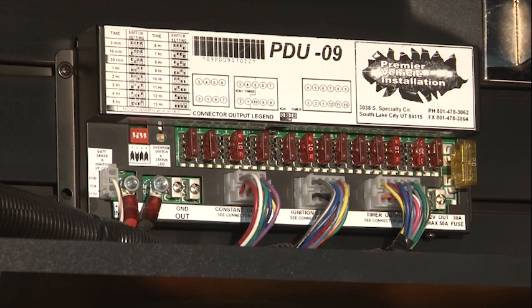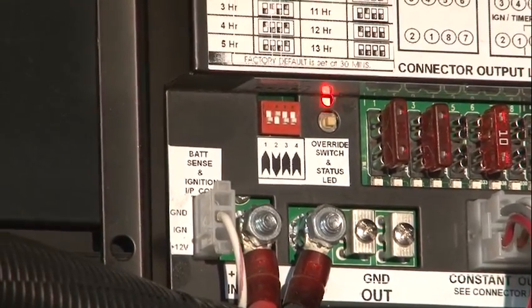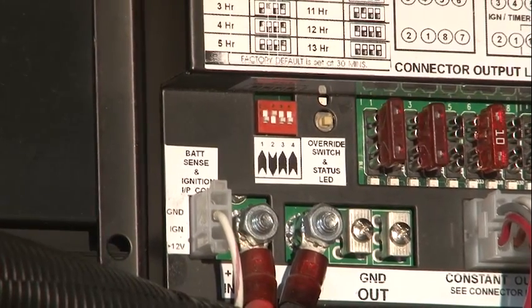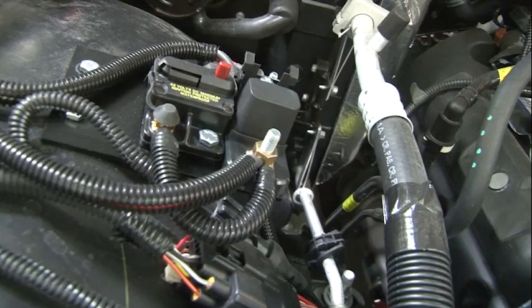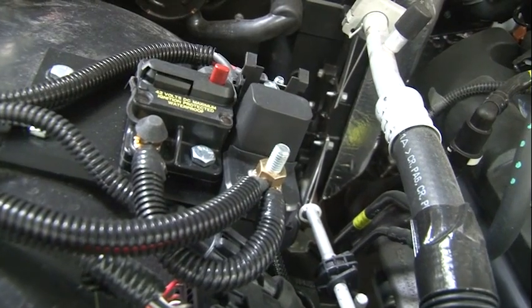On the front side, so it's easy to access, are your dip switches for your timed outputs, and they can be adjusted from a 2-minute timed output up to 13 hours. We run this all off a circuit breaker, 6-gauge wire that goes up to the battery.